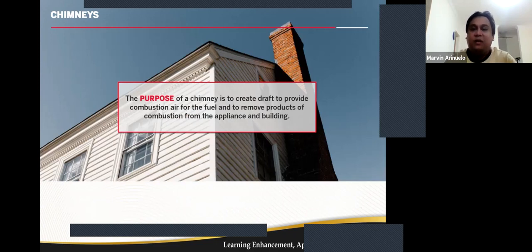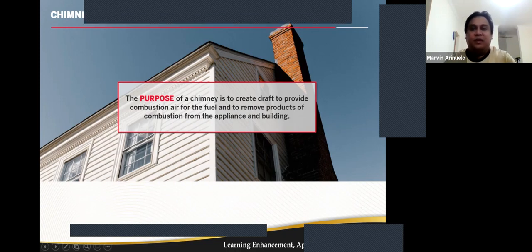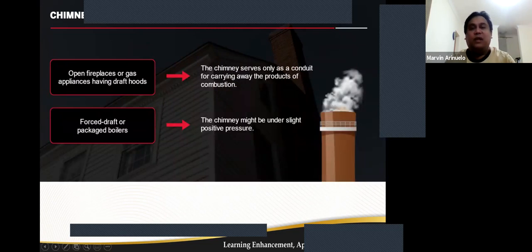Let us discuss the chimney. The purpose is to create draft to provide combustion air for the fuel and to remove products of combustion, the ashes and the like, from the appliance and the building. For an open fireplace or gas appliance having a draft hood, chimney draft has very little influence on the combustion process. The chimney serves only as a conduit for carrying away the products of combustion. For a forced draft or packaged boiler, the chimney might be under slight positive pressure and again serves only as a duct to carry away the products of combustion.